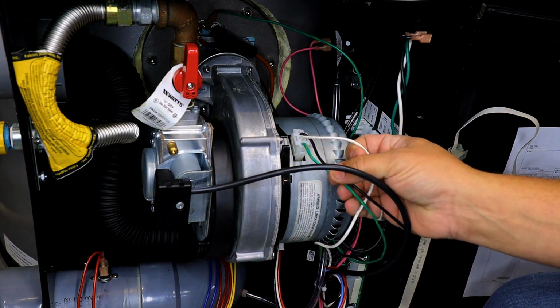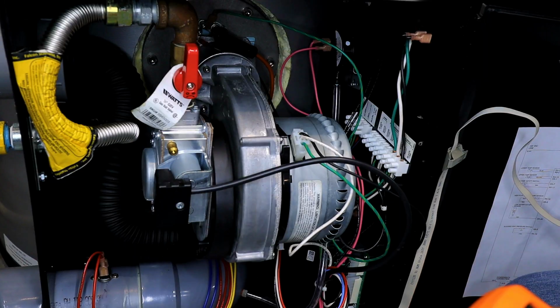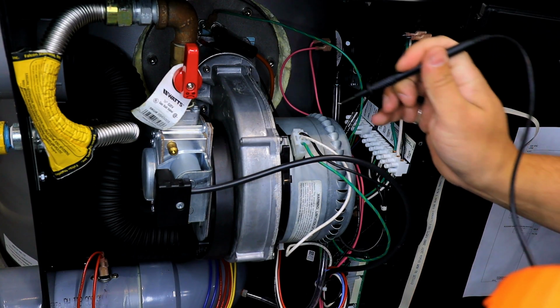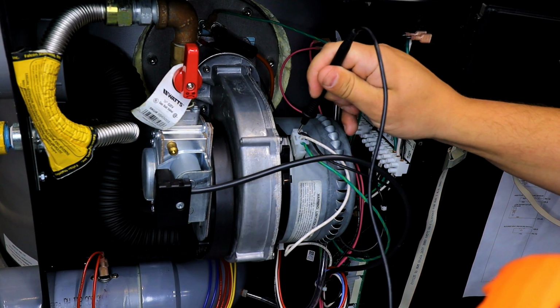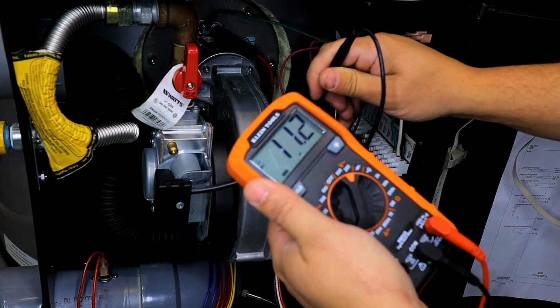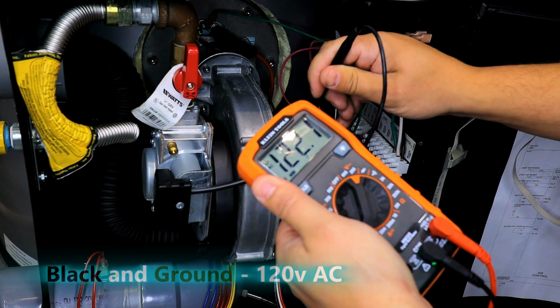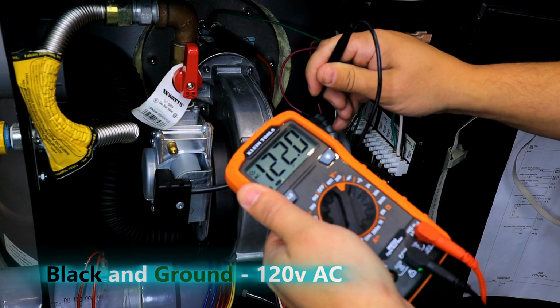This one at the top with the green, black, and white is going to be our high voltage input. So just to confirm, we can take our lead and place it on the black wire and then ground off the other side to see that we do in fact have 120 volts at our motor.